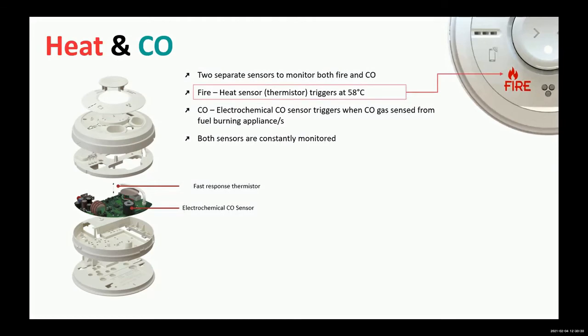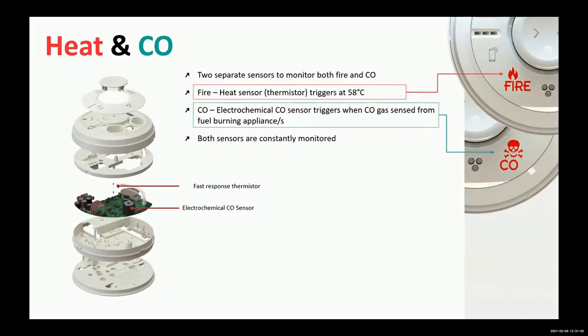Now, I suppose the perception out there is that the reaction for 2 different types of detection is the total opposite. For a fire situation, you seal in a room. For carbon monoxide, you ventilate a room. Okay, so it's very important that we have identification on the device as to which element of that alarm has activated. So we bring the element out through the cover. If it's a fire, we bring the fire out through the cover, so it's a visual indication that the fire element of that device has activated the system. If it's CO, we bring the skull and crossbones out through the cover, so that indicates that it's carbon monoxide that's activated that device. Okay, again, it's very, very important.